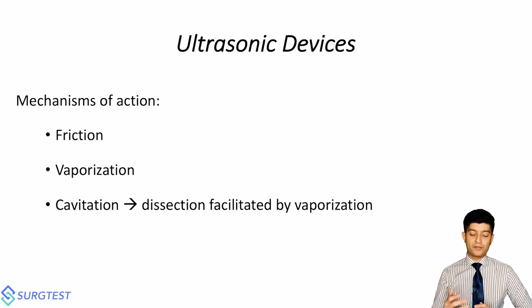The vessel sealing occurs as a result of coaptation. We've covered this. The proteins get denatured. There is a coagulum that forms across the intima. This is the same mechanism of action as a vessel sealing device, a bipolar vessel sealing device. But the main difference is this entire magic is happening by means of physical friction rather than friction caused by the oscillation of electrons. When you are using an ultrasonic device, there is no electricity that is flowing across the patient. Whereas for monopolar and bipolar devices, there is electrical energy that is flowing across the patient.